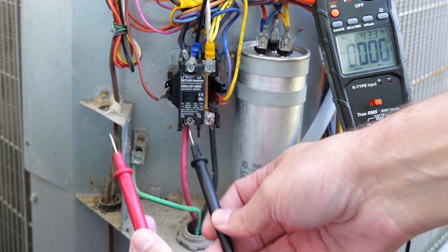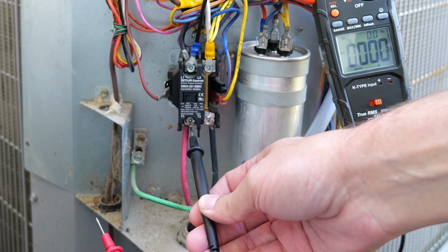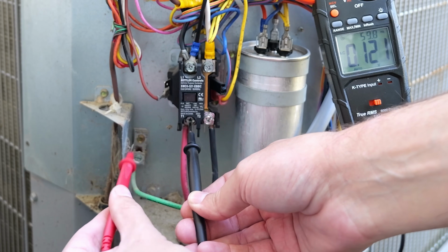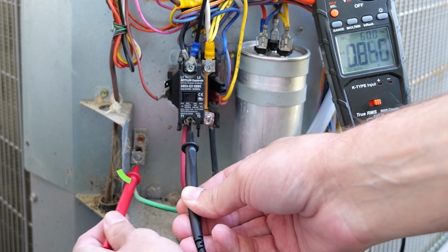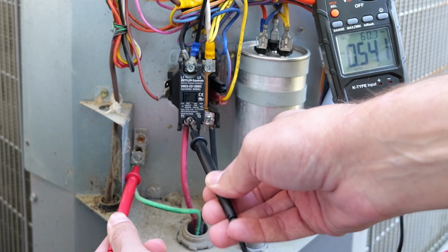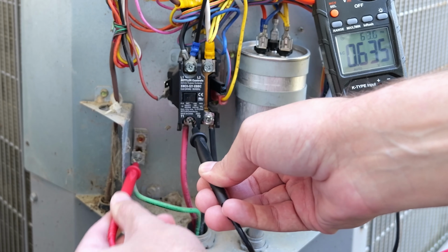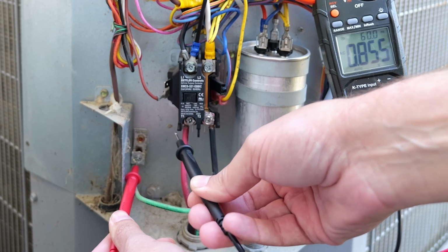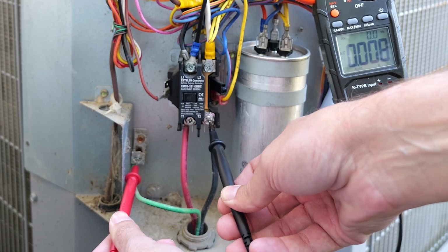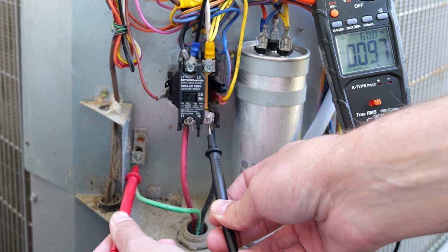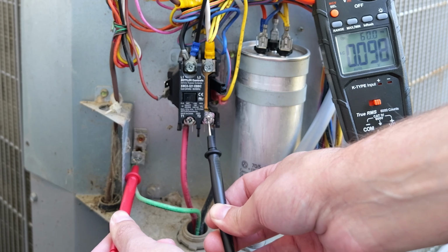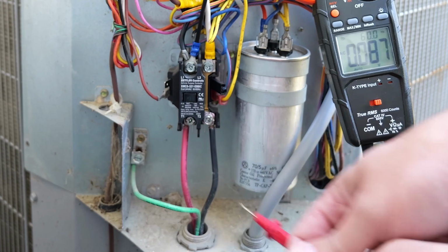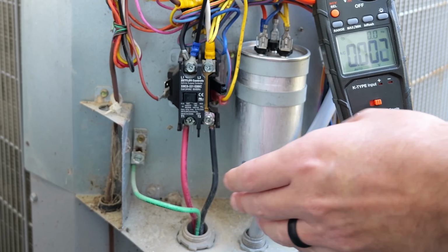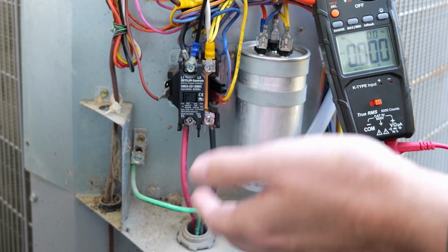Now I want to check each side of my contactor. I'll start on the left side of my contactor and go down with my other probe to the ground, and as you can see, we've got 0 volts there. I'll leave the one probe on the ground, move my other probe on the contactor over to the screw on the right side, and as you can see, I'm still getting 0 volts. So this is in fact turned off, there is no power flowing to it. At this point, I feel comfortable to start working on it.